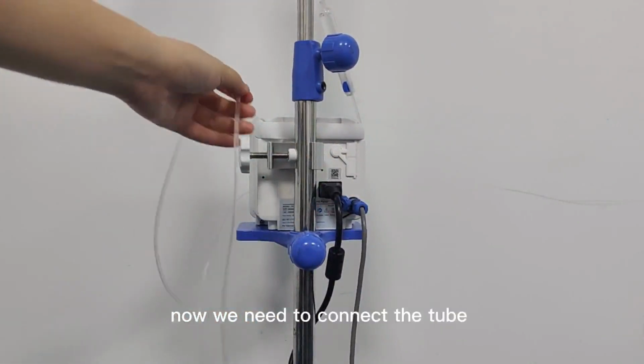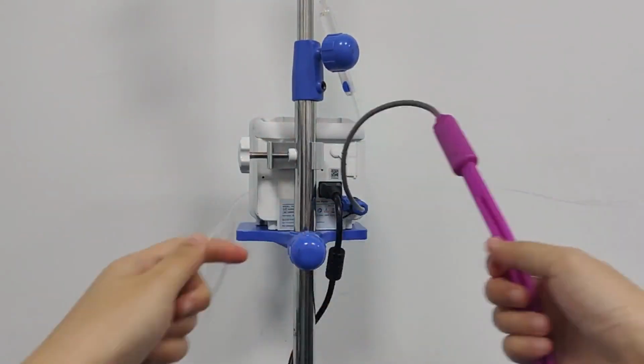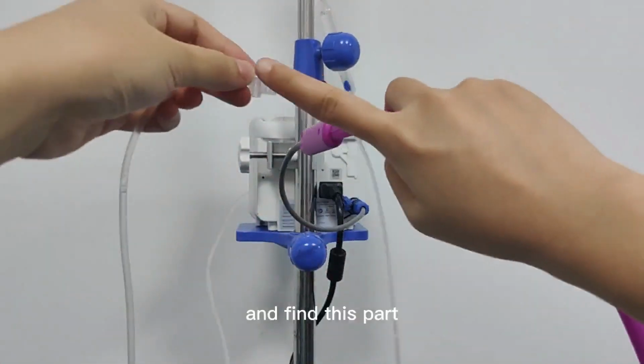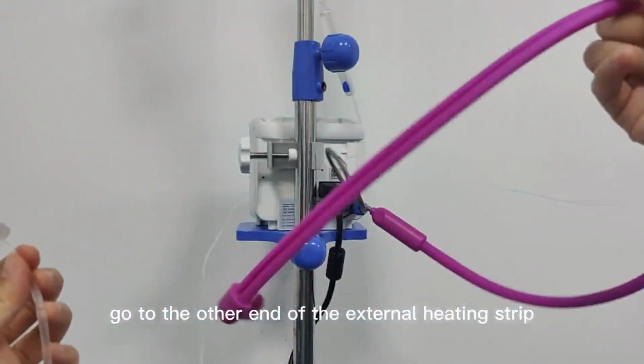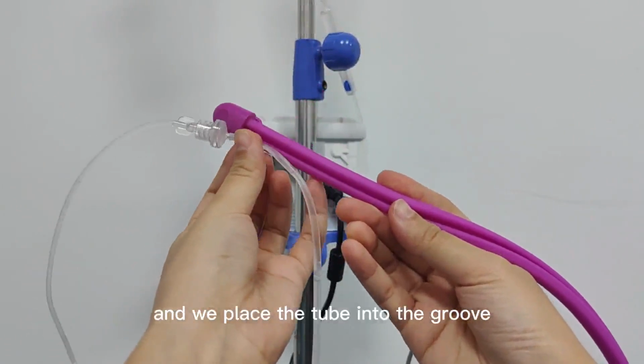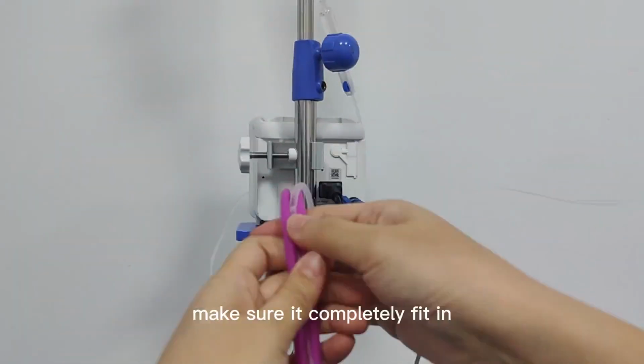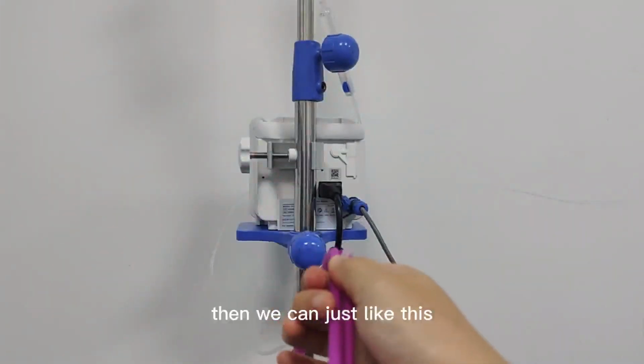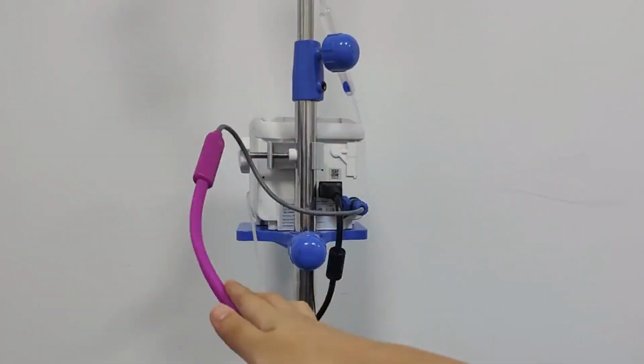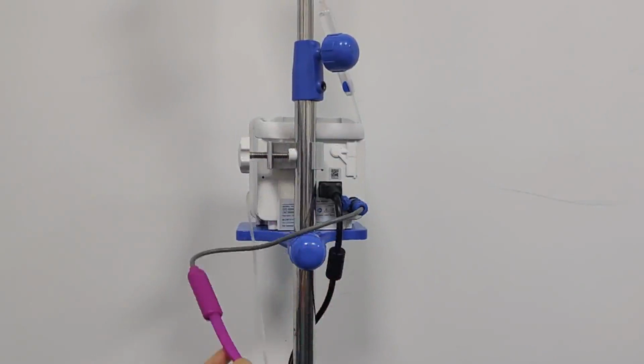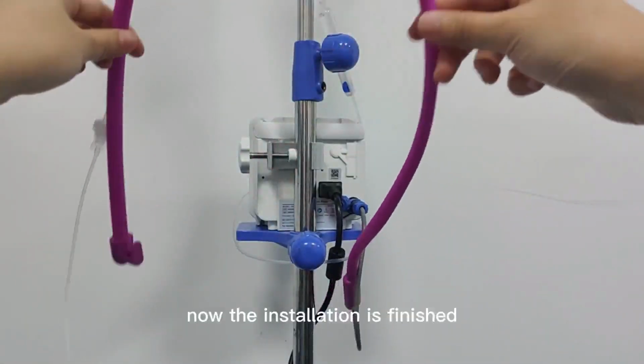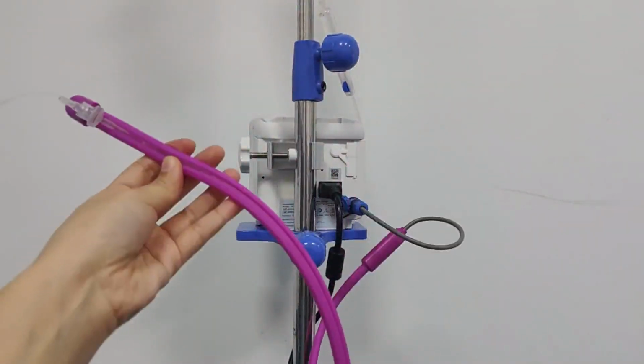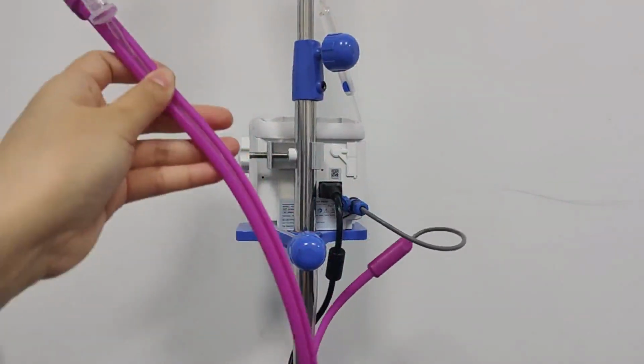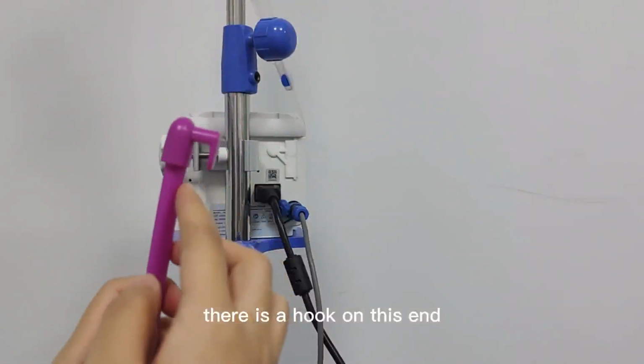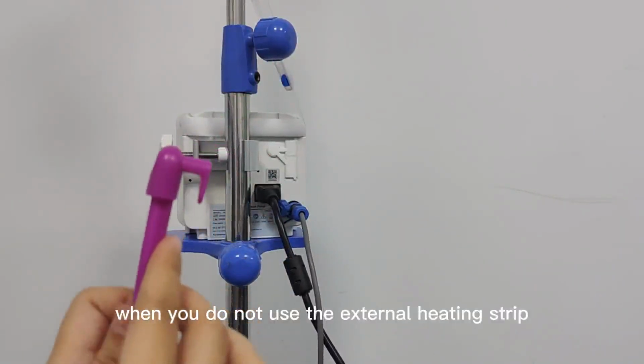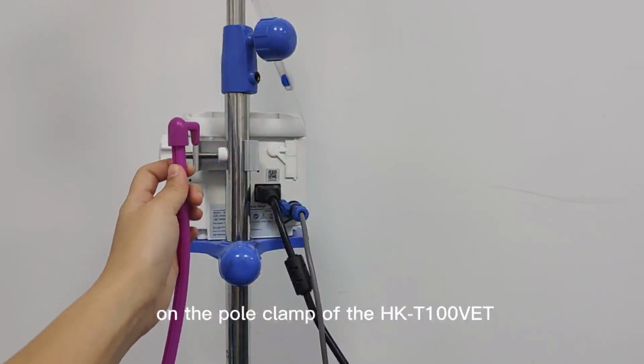Now, we need to connect the tube to our external heating strip. First, we find the needle and find this part. Go to the other end of the external heating strip and we place the tube into the groove. Make sure it completely fits in. Then we can just do it like this. Now the installation is finished. When the heating function is on, the whole section of the tube will be warmed by this external heating strip. There is a hook on this end of the external heating strip. When you do not use the external heating strip, the hook design allows you to hang it on the pole clamp of the HKT100VET.